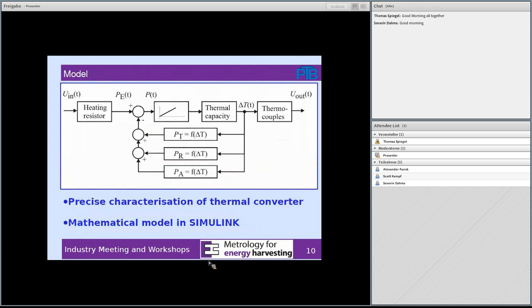So this gives us a model of the thermal converter. You have here the thermal capacity. You have here the integral of the power, and the power is the electrical power which is transferred by the heater resistance to thermal energy or power. And we have here some feedback which gives the heat flow I just explained through the thermocouples, through radiation and through the air. And then it comes out with our temperature rise, and the thermocouples convert this to the output voltage.